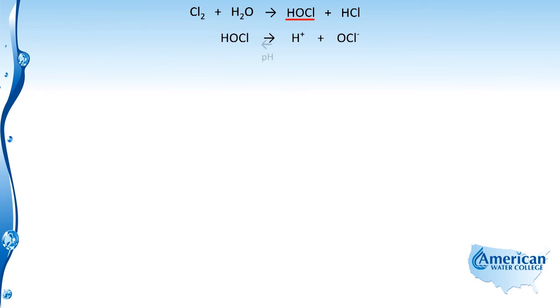This reaction goes both ways and is pH dependent. As pH is lowered, the equilibrium shifts, favoring the formation of hypochlorous acid, which is about 100 times more effective as a disinfectant than the hypochlorite ion.